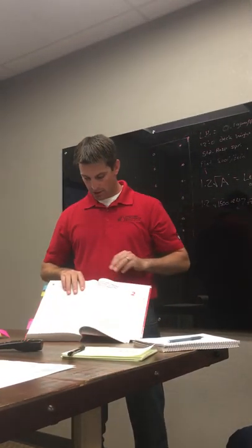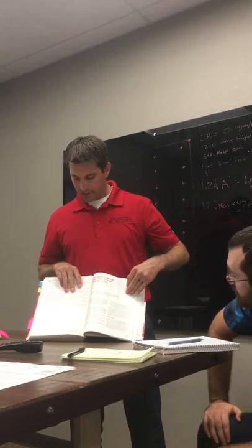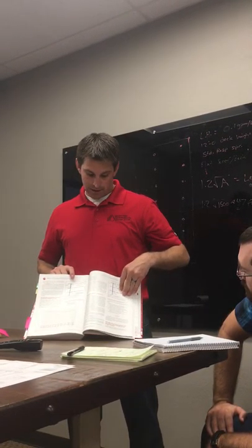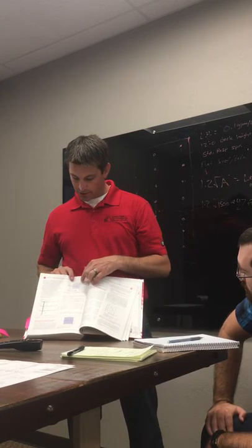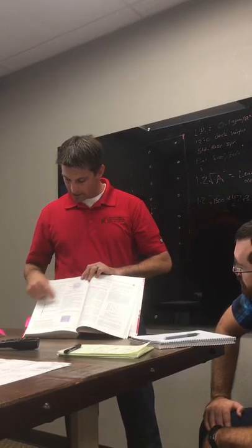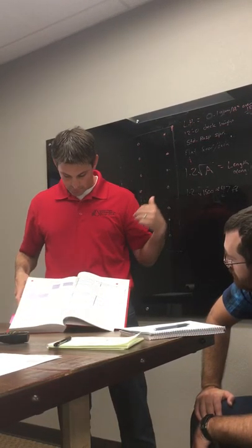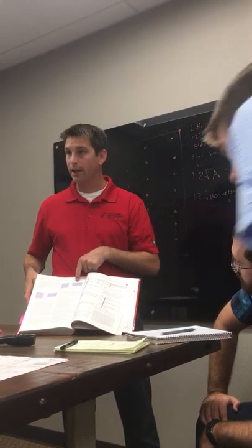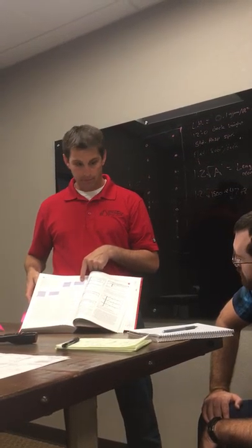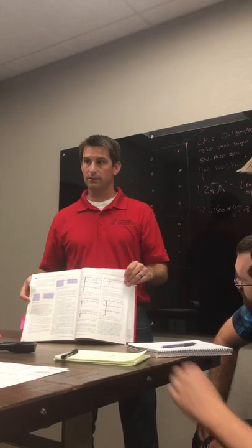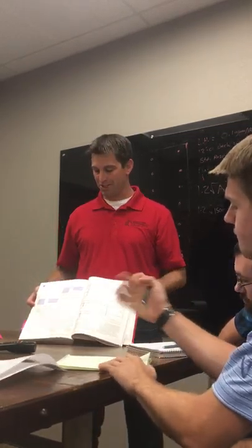It's awesome. Step by step hydraulic calculations. They walk you through a little example, and they tell you exactly what I just showed you of how to draw your rectangle, which head you pick up next. And they even give you that formula: 1.2 times the square root of A is your length. They explain it a little bit too, so I recommend you all go read through that when you get done. It's always fun to read code books.